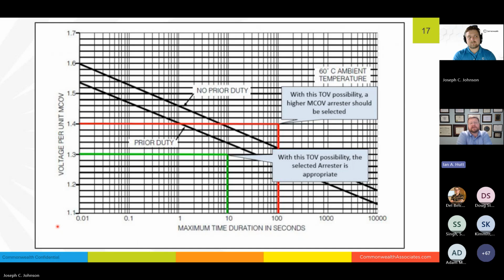However, if our clearing times go higher because of protection, because of schemes and other things, we'll notice that the per unit MCOV value will drop for TOV concerns. And this is a graph that we'll see for most equipment that's out there.